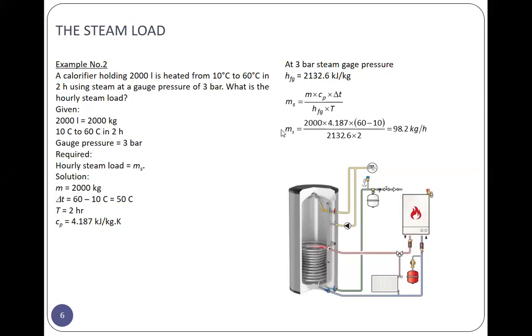So M_s is equal to M times Cp times delta T over h_fg times t, which is 2,000 times 4.187 times 60 minus 10, or 50, divided by 2132.6 times 2, which is equal to 98.2 kilograms per hour. This is the required steam flow rate. The condensate flow is the same, it's included here.